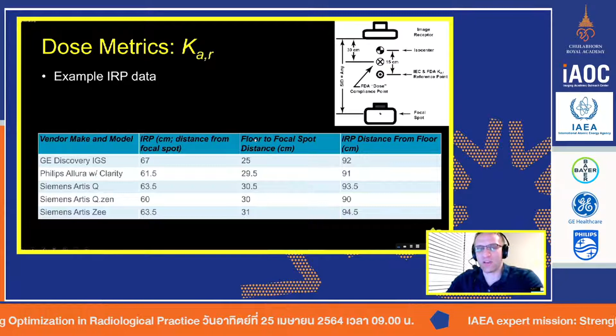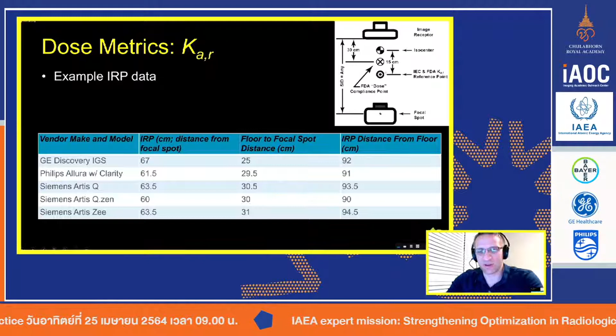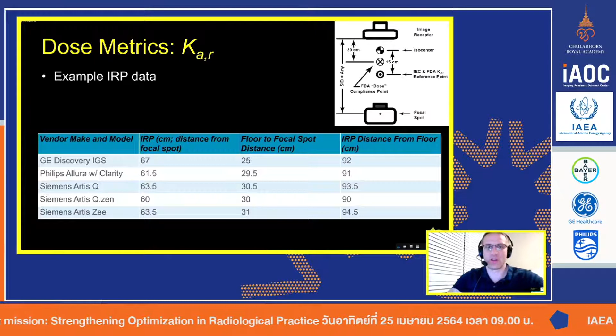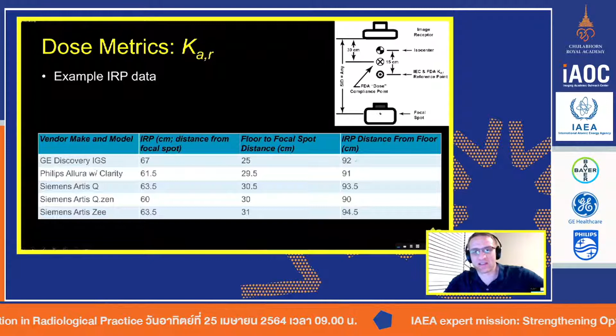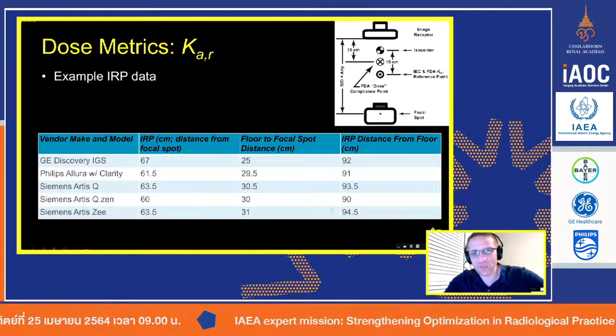A value that might be more interesting is the international reference point to the floor. That's just because you don't always know exactly where the focal spot is on every machine, but you'd obviously know where the floor is. So if you measure from the floor up, for example on a GE Discovery IGS, it's 92 centimeters from the floor to the international reference point. So here I just gave you some values, and these values will be important in a little bit when we go to calculate patient's dose, and I'll show you how to do that in a couple slides.